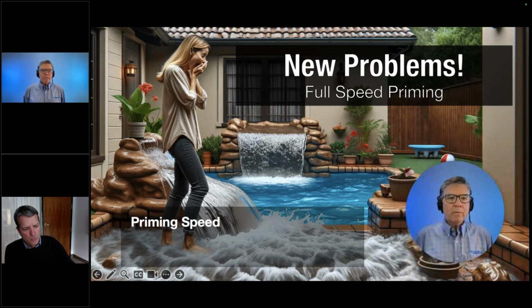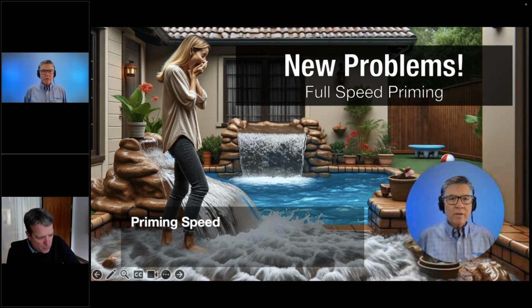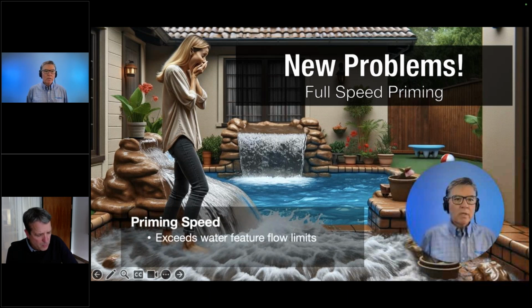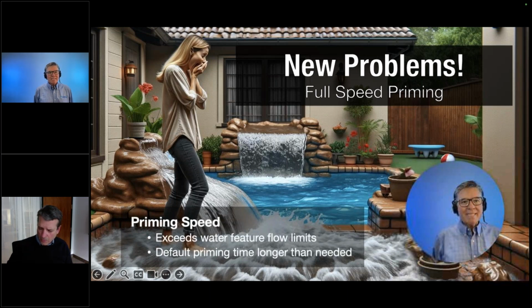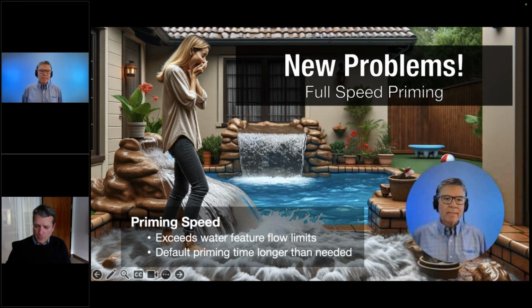If you need it, you need it, but if you don't, this is something where you can either slow down the priming speed or reduce the priming time to optimize it, so you're not tearing up the pump and making a bunch of noise during a priming cycle that the application doesn't call for. And so again, in this, it exceeded the limits of a particular waterfall.